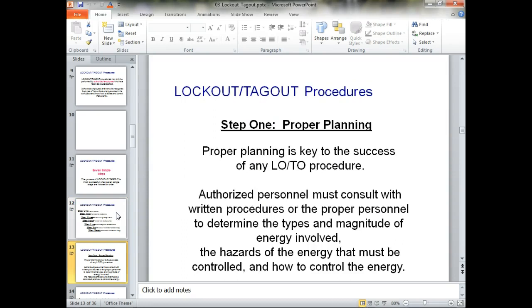So we're going to do lockout, tag out. Y'all will do the tag out, and I'll do the lockout. When we put power on, you'll see me take the key, turn it, pull it out, then turn it back to the left position. So as soon as you hit that E-stop button, it's locked out, meaning I don't have to come put a lock on there, it locks out automatically when you push the button. But I always verify to make sure. Once you put your tag on and lock, and that button's pressed, what are you going to do? Verify it.